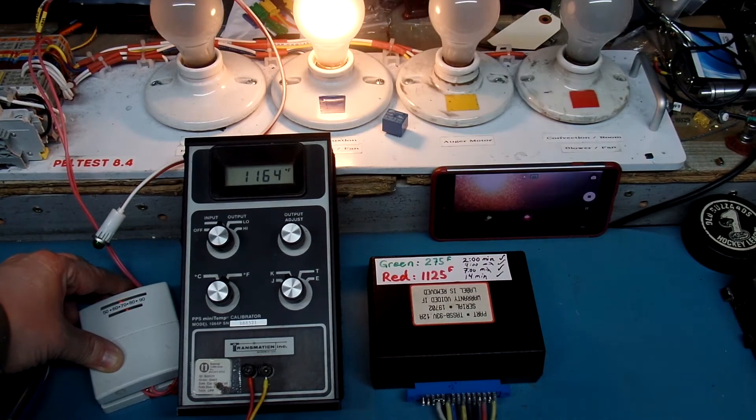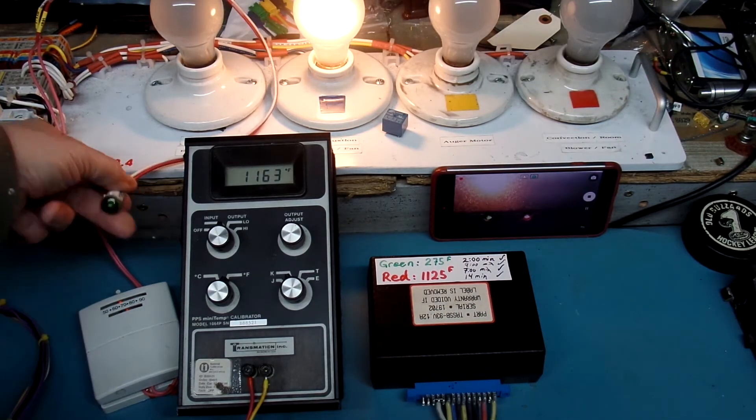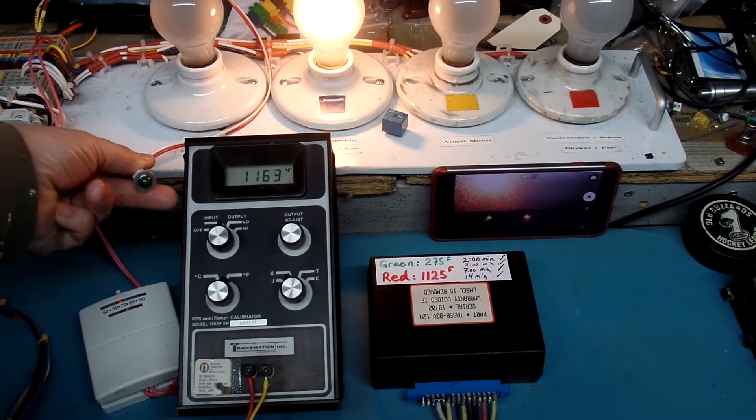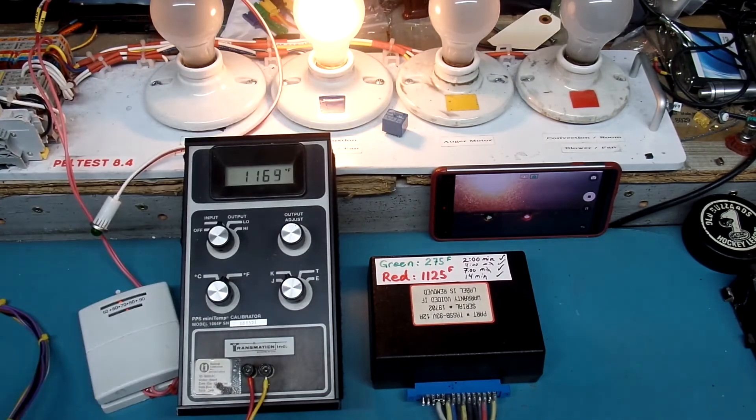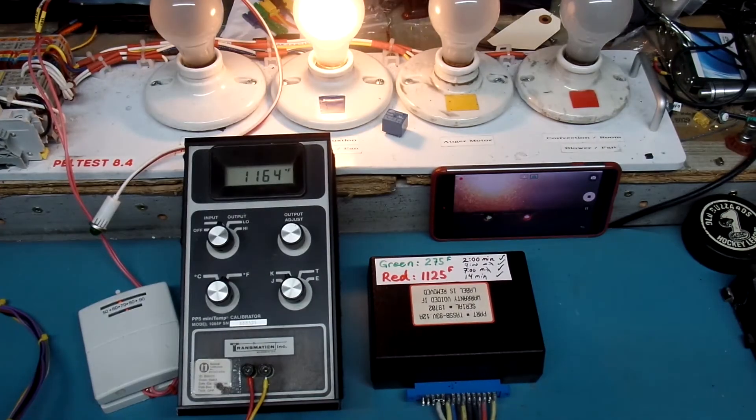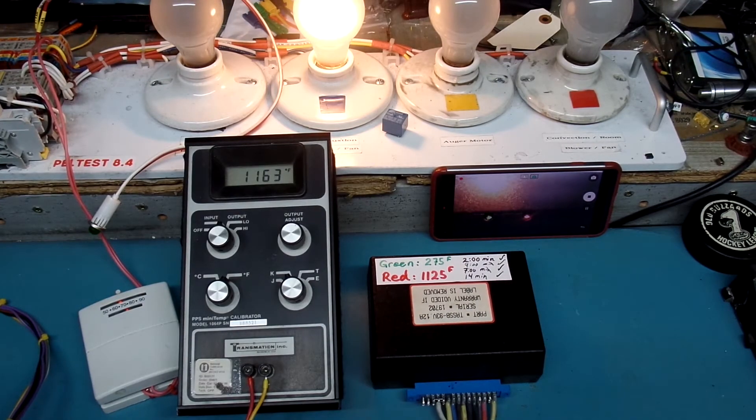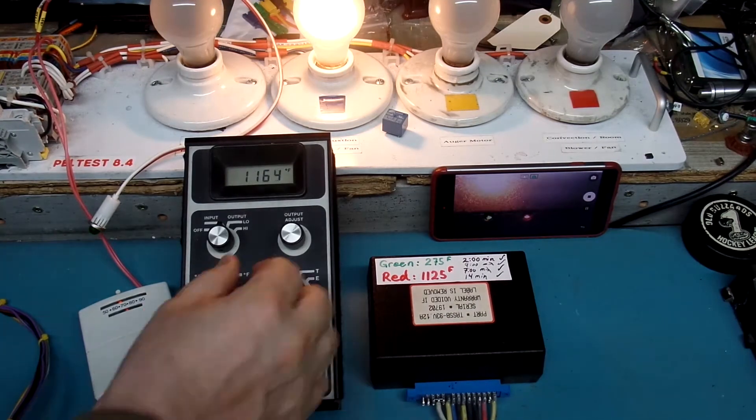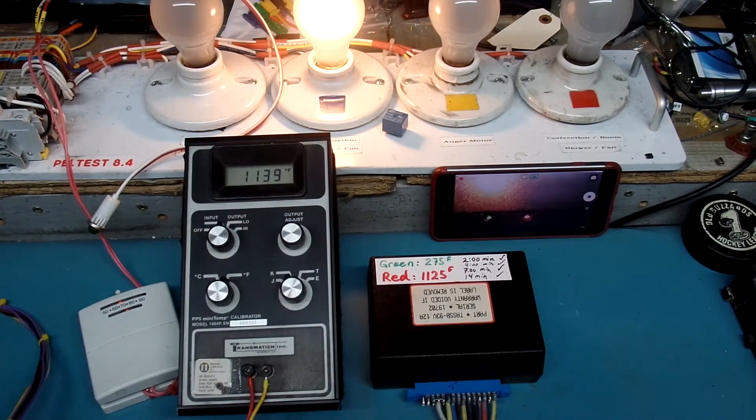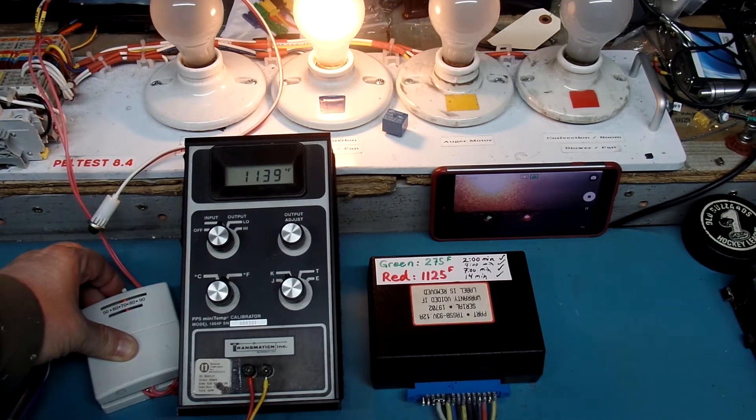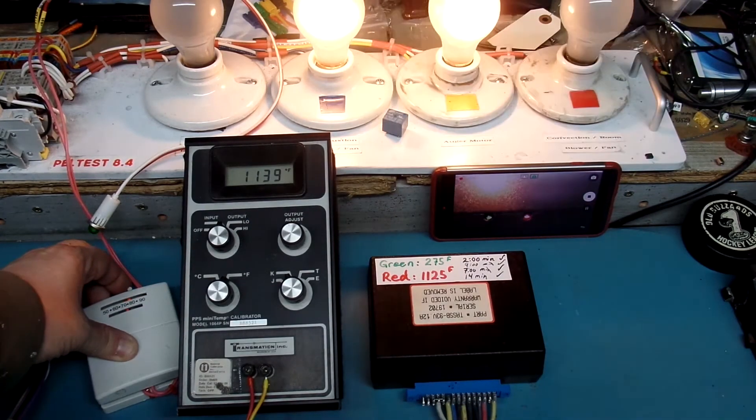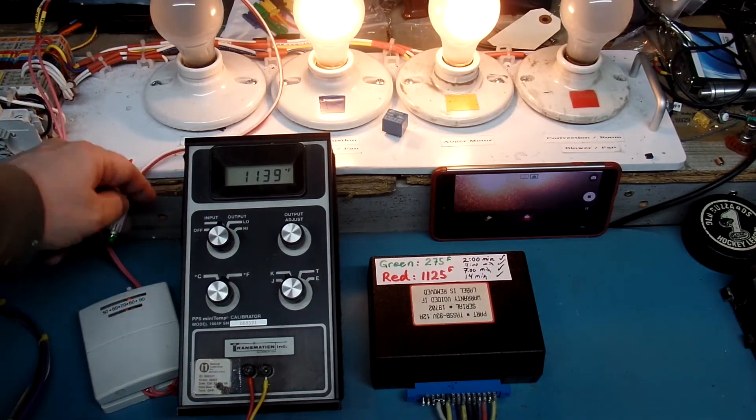So as it shuts itself off, we no longer get a call for heat and we see that the auger motor has stopped driving pellets. We'll stay in this way. The temperature of the fire will drop a little bit. We'll see that the room will also cool and the thermostat will come back into play and call for heat one more time.